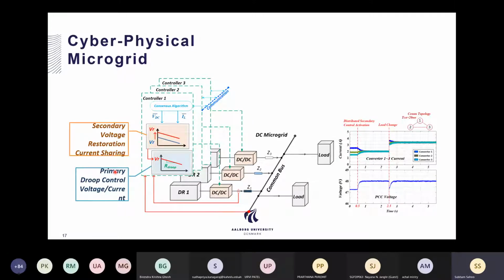If you've read about low-frequency droop control, you have the primary control, which is droop control, where you select the droop coefficients. The droop variables in this case are voltage and current. Because of the droop, you will never be operating exactly at the reference. That's why you go for the secondary controller, where you try to restore the voltage, and you can also achieve current sharing between all the converters. That's the purpose of the secondary controller for the DC microgrid.